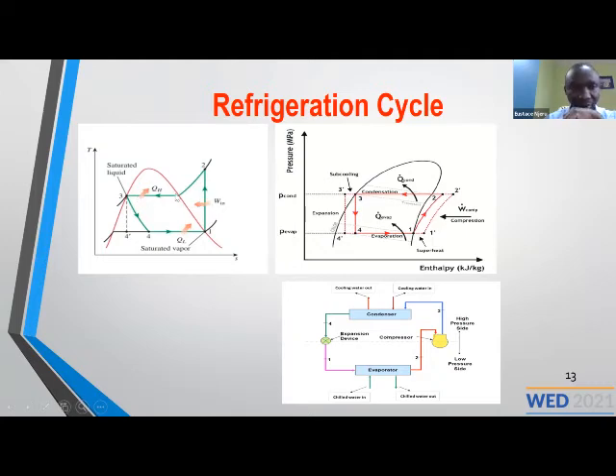At the same time, if you monitor the conditions at the condenser, where you are using the cooling media, you can monitor the temperatures. If it's air, on a cool day in a cold environment, the air is cool, so you can monitor that air and reduce the amount of work being done by the compressor, because you can operate at a slightly lower temperature by doing what we call condenser temperature reset.